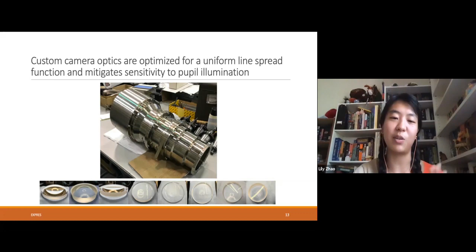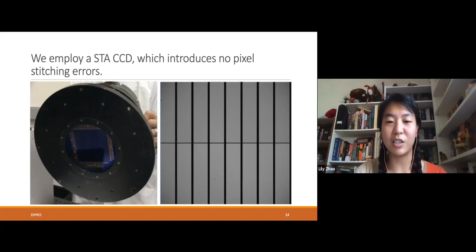And lastly, we used what was at the time fairly new technology, an STA CCD detector. This detector is huge and was manufactured in such a way that all the pixels were laid down at one time. Before, a big concern was that pixels would be laid down in blocks next to each other. But if there's any error in how the blocks were laid down, they might have shifted a little bit. And then as the photons pass back and forth across these borders, the shift would be inaccurate because the pixels, which are assumed uniform, wouldn't actually be. So instead, we opted for this large detector, which has none of these stitching errors.